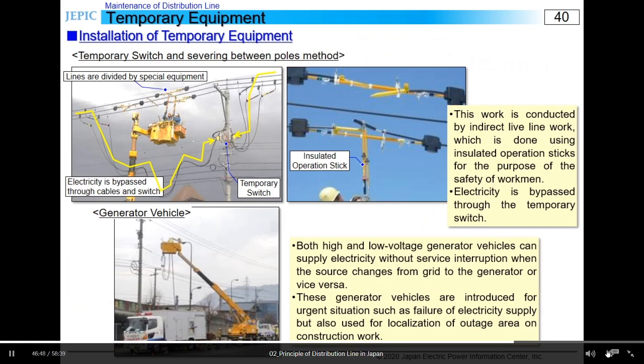These are the pictures of the method I explained in the previous slide. The two upper pictures show the situation of installing a temporary switch and the line cut between poles. Before the line is cut, a bypass route is formed by temporary cable and switch, as shown in the yellow line. Then the line will be cut in the middle of the span between poles by giving the tension of the line to a special equipment.